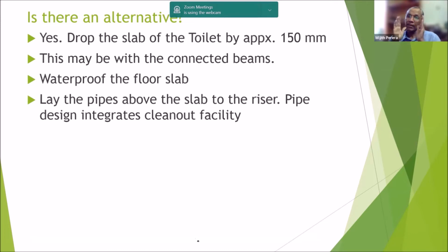The pipe design essentially must have another feature which we call clean out facilities, because the piping system we are going to install in this toilet is not going to be accessible from bottom, nor will it be accessible all over the place from the top. Therefore, it is very important that we think of future maintenance when designing this system and provide adequate facility for maintenance, particularly in the sewer and wastewater systems, to clean out in the most unlikely case of having a blockage. Because if you design your system correctly, believe me, you will not have blockages.